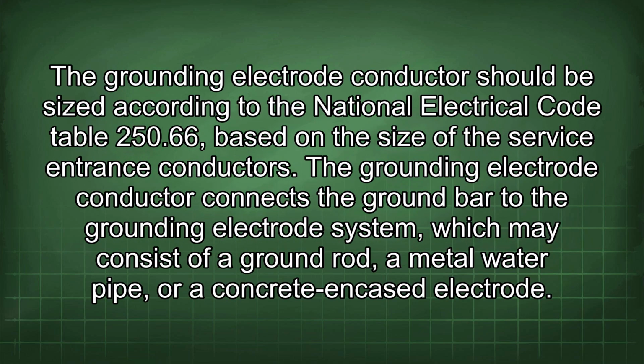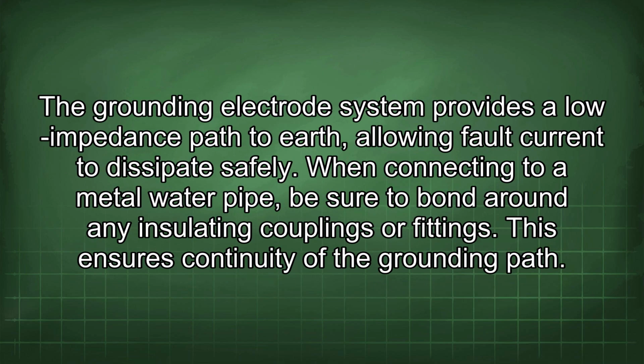The grounding electrode conductor should be sized according to the National Electrical Code Table 250.66, based on the size of the service entrance conductors. The grounding electrode conductor connects the ground bar to the grounding electrode system, which may consist of a ground rod, a metal water pipe, or a concrete encased electrode. The grounding electrode system provides a low impedance path to earth, allowing fault current to dissipate safely.